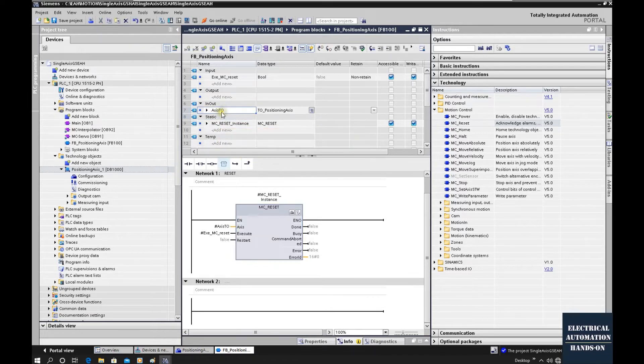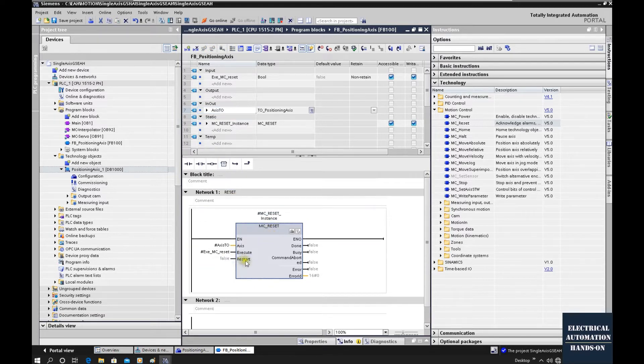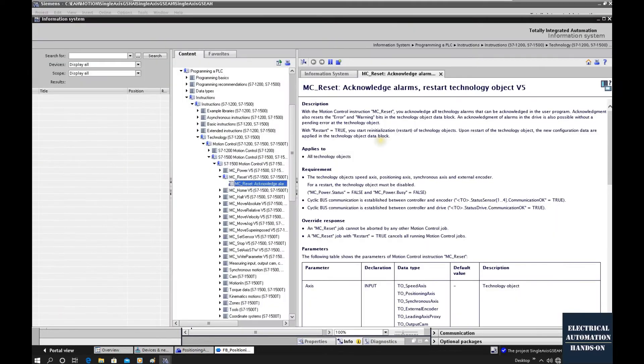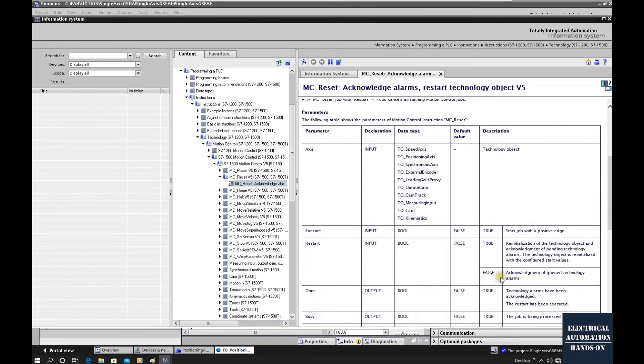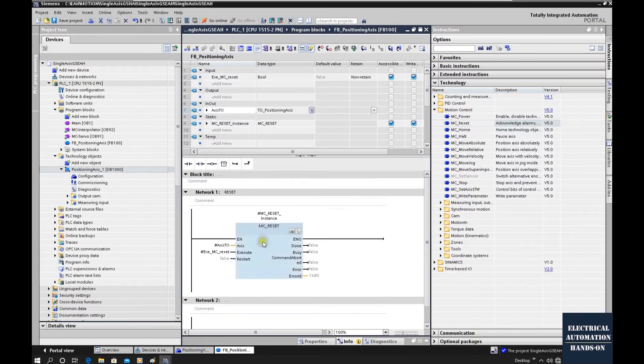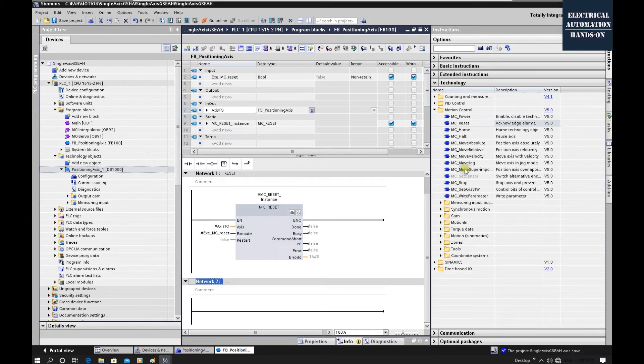We can name it 'axis_TO' and see it automatically updates — very handy. To check the details of MC_Reset we can press F1. For the restart parameter: by default it is false, meaning once we execute MC_Reset it will acknowledge the queued technology alarms. If set to true, it will initialize the TO. In most cases we leave this as false — we only need to acknowledge the fault.